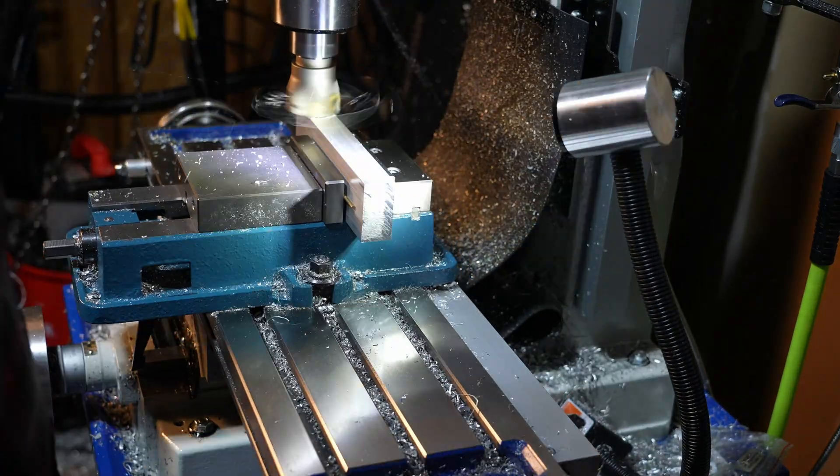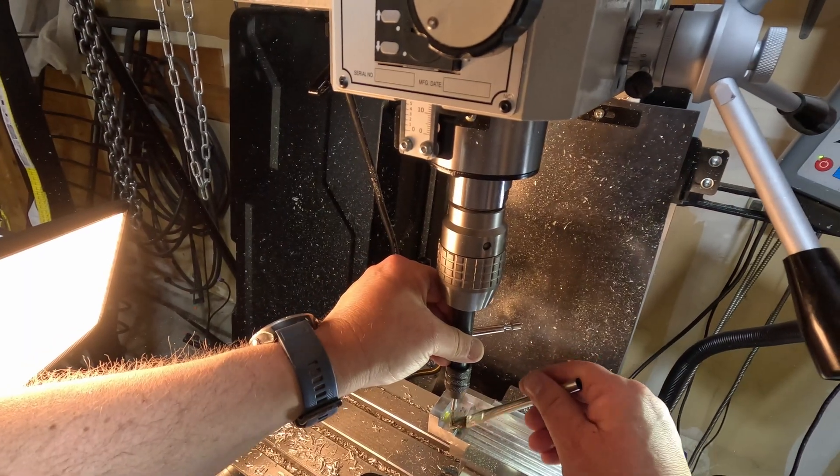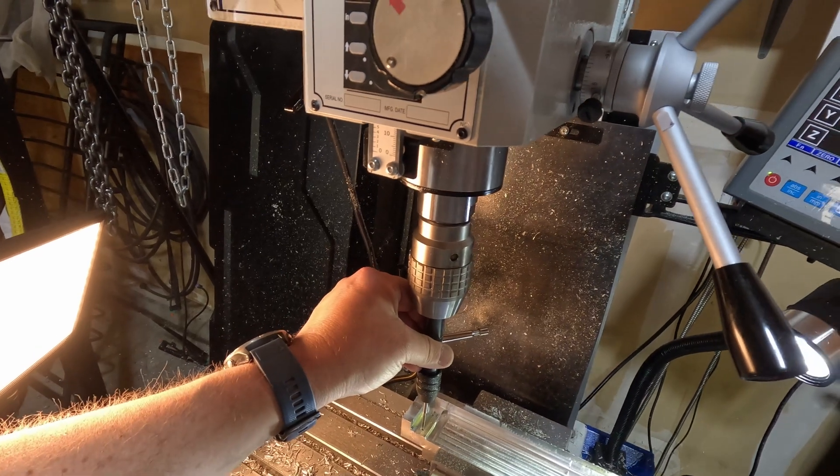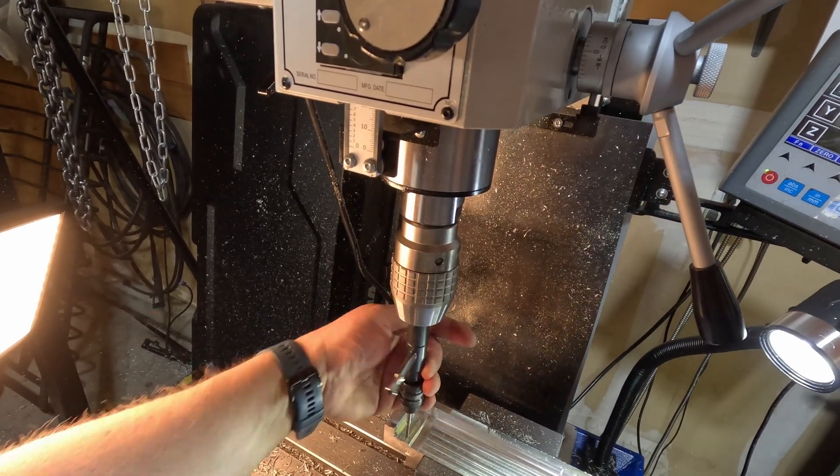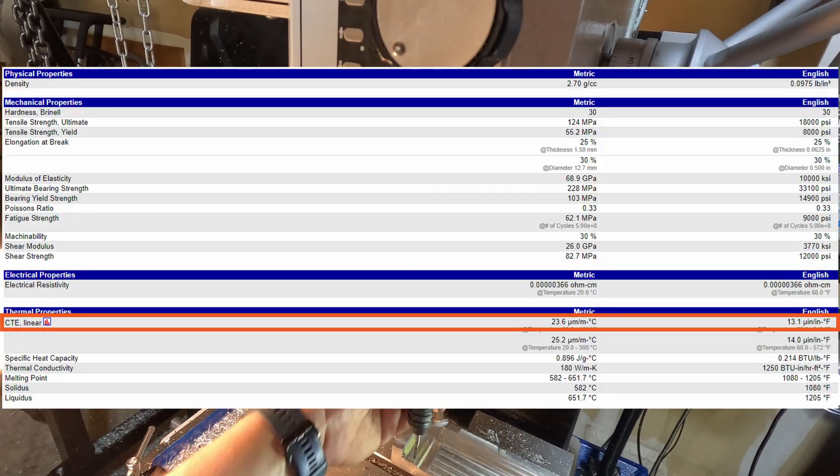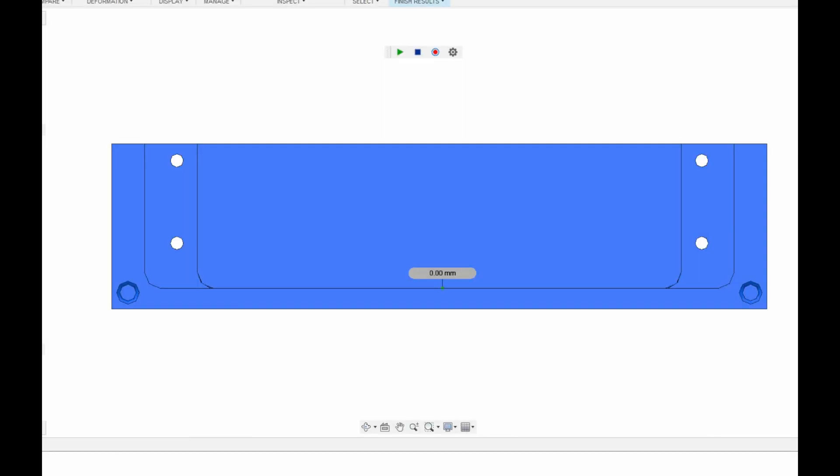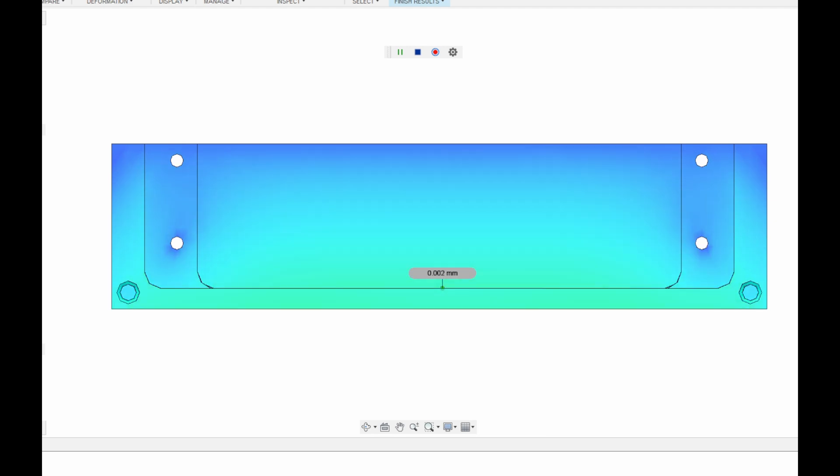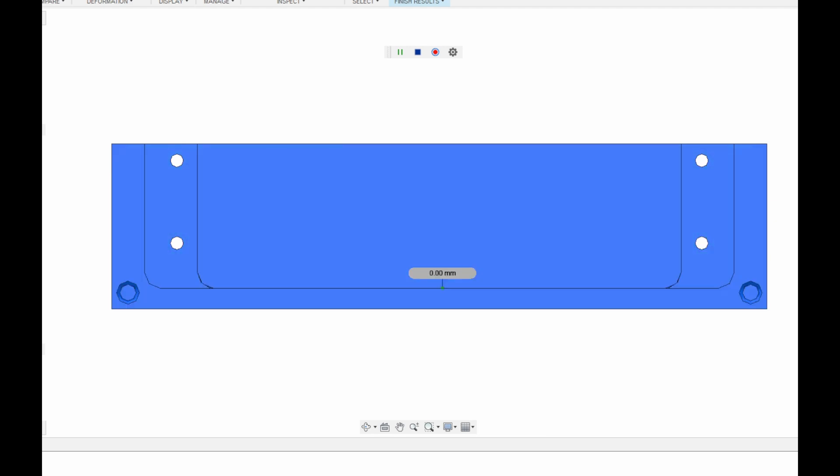I made this one from a block of 6061 aluminum because that's what I had on hand. Unfortunately, the realities of this choice introduce our first little challenge. And that's because aluminum has its own thermal expansion of about 22 ppm per degree C. Which means the null block is going to be growing and shrinking as the temp varies during the test.